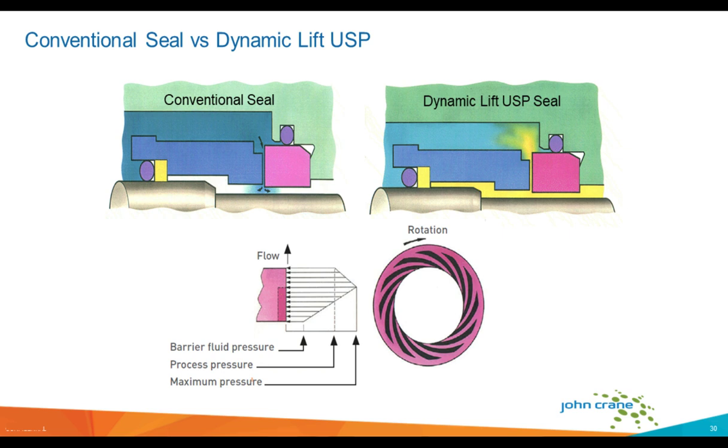So the maximum pressure always occurs at the outside diameter of the grooves, and it's always higher than the process pressure when the seal is operated within its parameters and it's in a dynamic state.